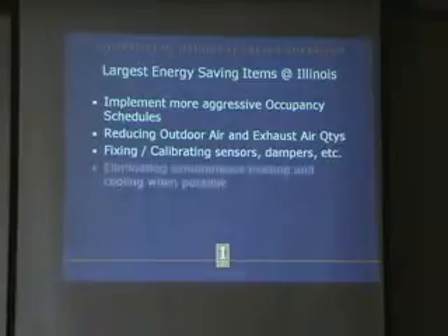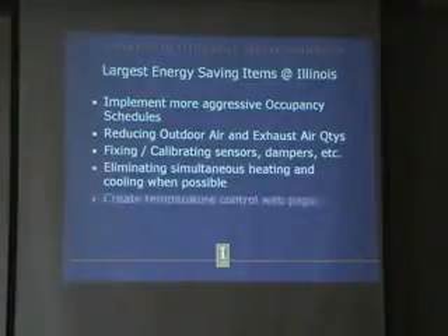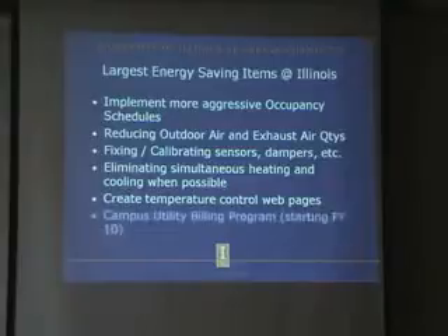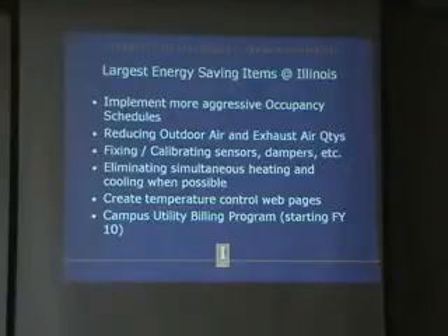These are some of the largest energy-saving things that we've been able to implement: implementing more aggressive occupancy schedules, reducing outdoor air and exhaust air quantities, and lots of maintenance work—fixing and calibrating sensors, dampers, all the maintenance things that need to be attended to for them to work properly. We've kind of touched on some of the simultaneous heating and cooling things that are out there.